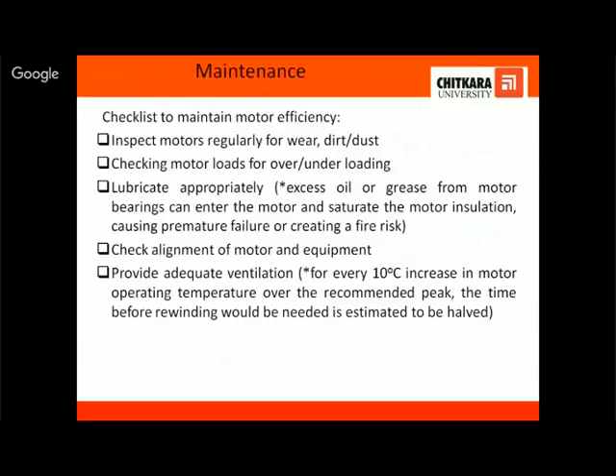Then lubricate appropriately. Lubrication should be proper. Even excess lubrication is harmful. It may saturate the motor insulation. Then alignment of the motor and equipment is very essential, and adequate ventilation is also required, because if the temperature increases, then the chances are that you have to go for rewinding of the motor because of insulation failure.